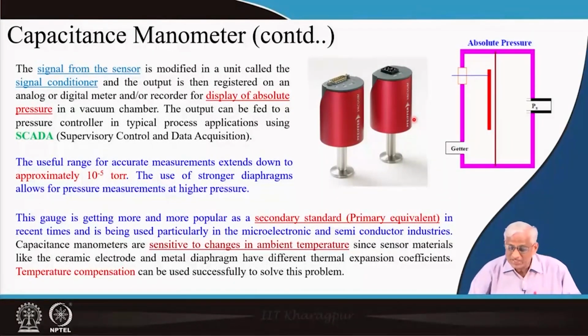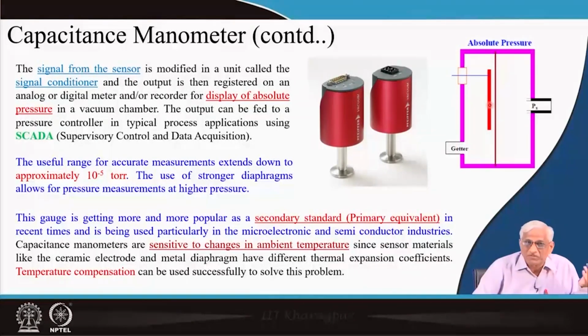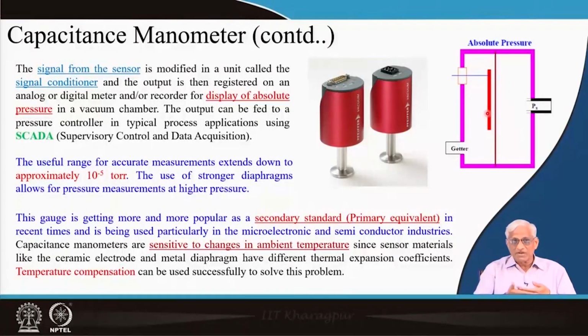Okay? So, this is an absolute pressure measurement with differential pressure, one side being 0 and sealed off, and capacitance will be converted into frequency. Why frequency? Frequency is one thing which can be measured to 1 in 10 power 8, 10 power 9, by the superheterodyne principle, etc. See, gigahertz, for example, microwave frequency, you can measure up to 1 hertz. That is why microwave frequencies are given for cell phones. Each customer will have one particular frequency, the next customer will have another frequency, slightly different. Bandwidth should be so high, but individual frequencies will differ only in the 9th digit or 8th digit. So, there will be input filters, and how to select these things, that is an electronic matter.